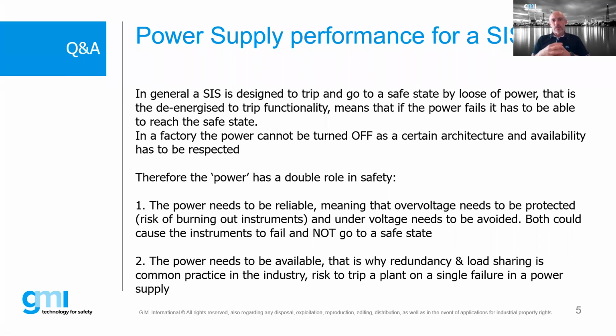So the SIS, of course, is designed to lose power, so the de-energize-to-trip functionality. It means that your hardware has to be able to reach a safe state. But the problem is that in a certain factory and so on, you cannot reach this off state. So the power has a dual role in safety. So it must be really reliable.